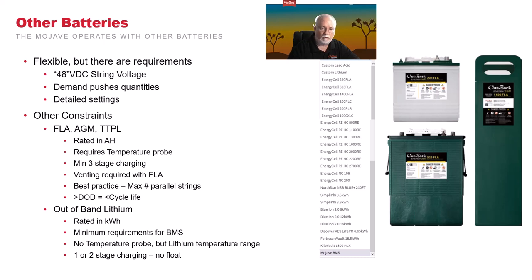There are other constraints, FLA, AGM, TTPL, VRLA batteries. They're rated in ampere hours. They require a temperature probe. There is 3-stage charging for those, and then venting is required with FLA generally.